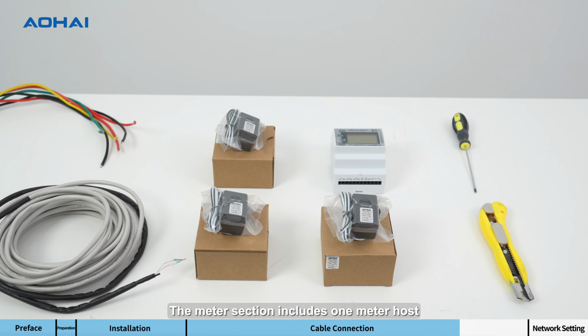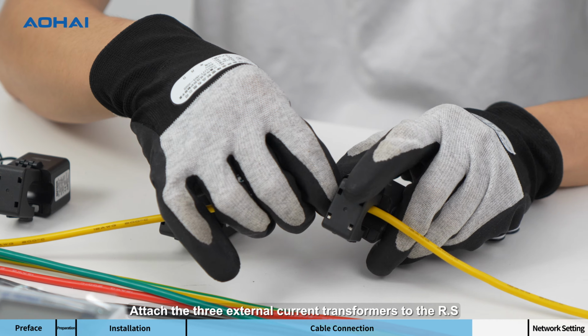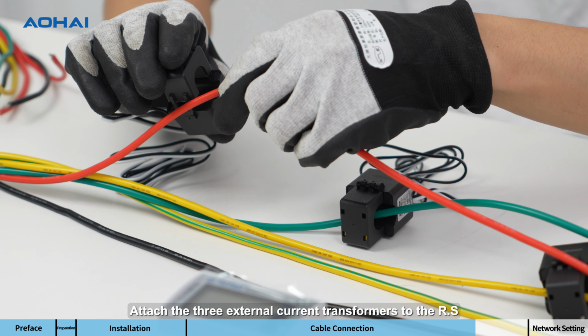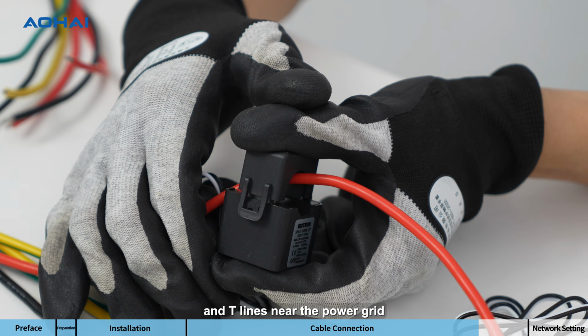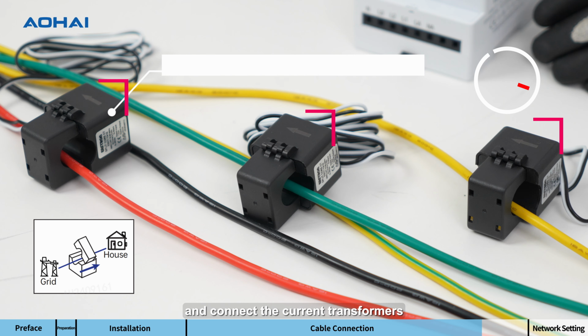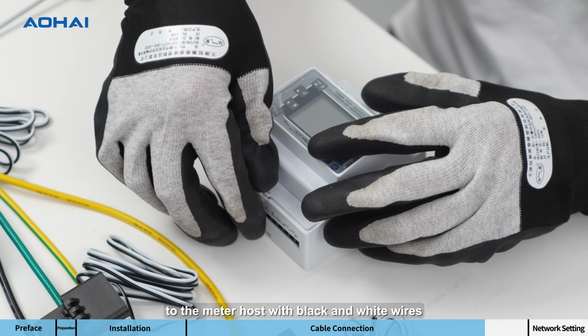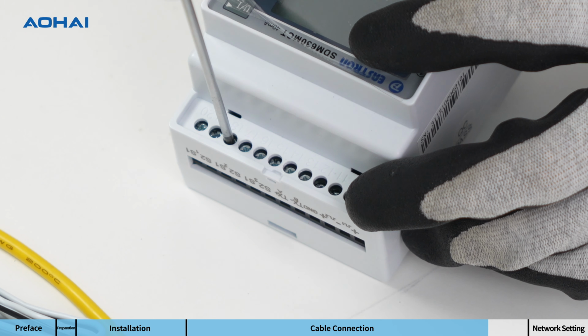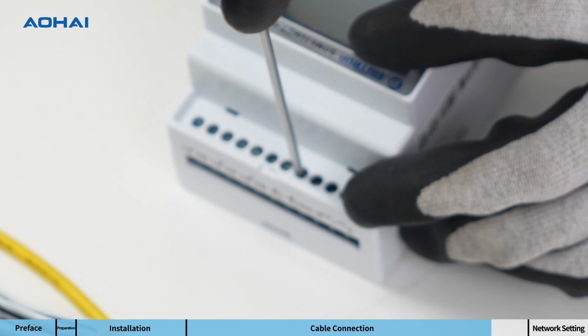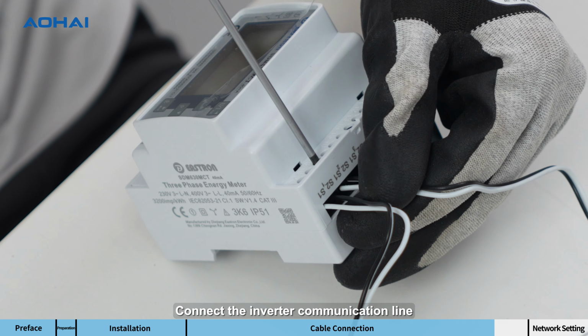The meter section includes 1 meter host, 3 external current transformers, and a 15-meter communication cable. Attach the 3 external current transformers to the R, S, and T lines near the power grid, and connect the current transformers to the meter host with black and white wires. Connect the inverter communication line.